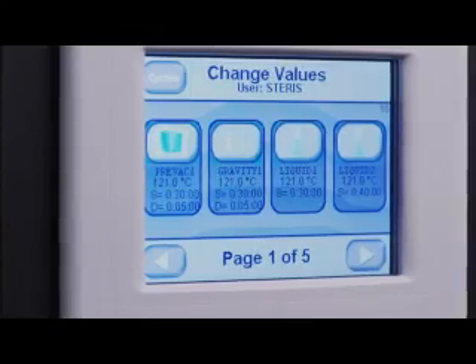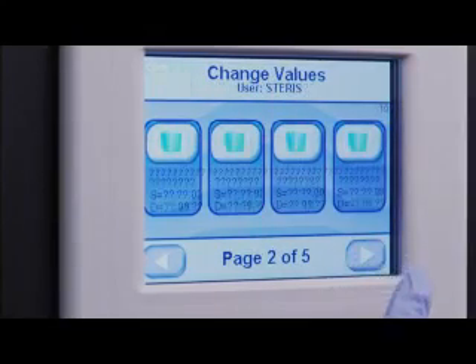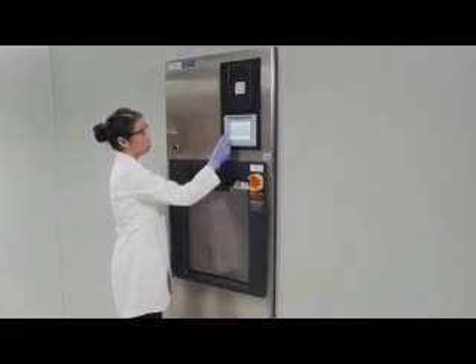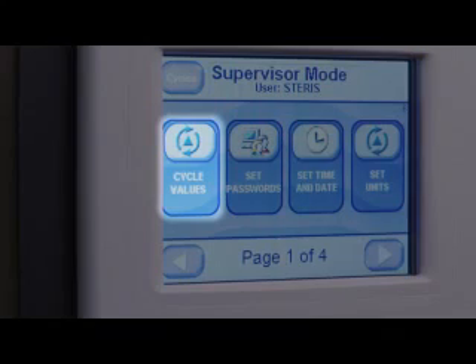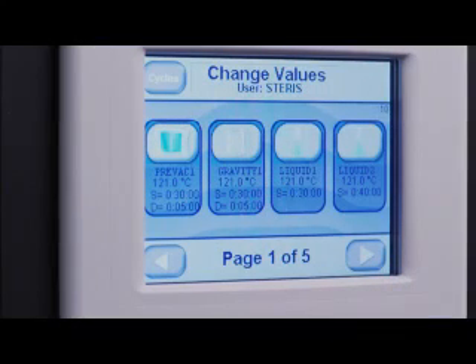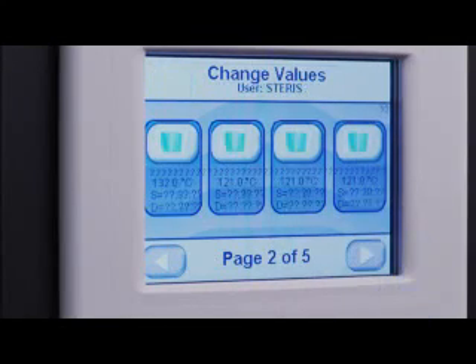The AMSCO Lab Series sterilizer is designed with 20 programmable cycles. Each cycle can be programmed per the user's requirements. Once in the supervisor mode, choose Cycle Values. From here, you will see the cycles that have been pre-programmed in the control. Each cycle is represented on the first screen, and then duplicate cycles have been set on the subsequent screens. Any cycle can be modified to be whichever cycle is desired.